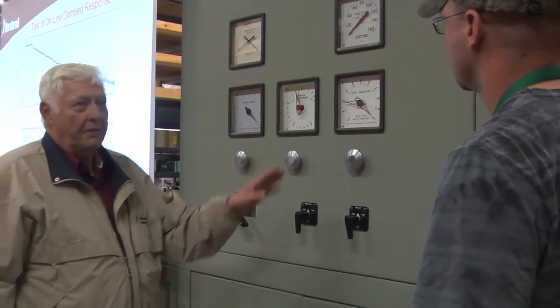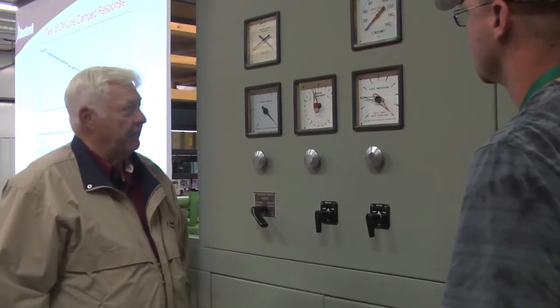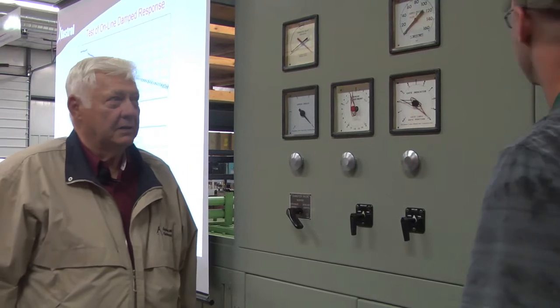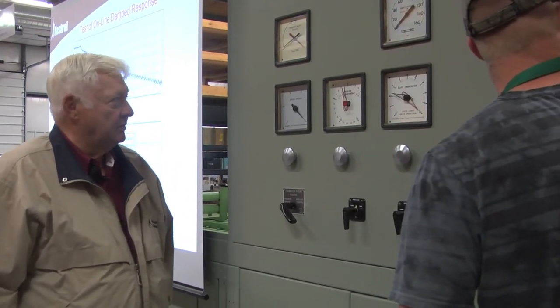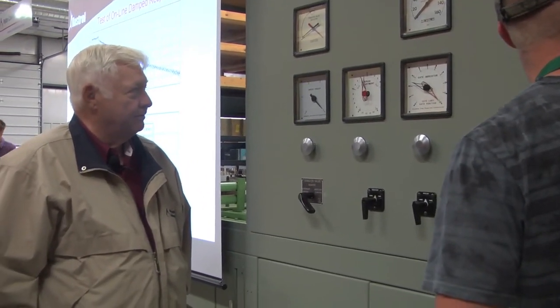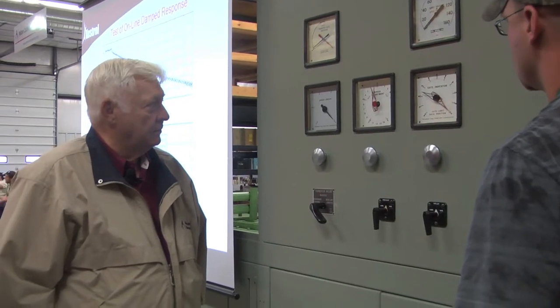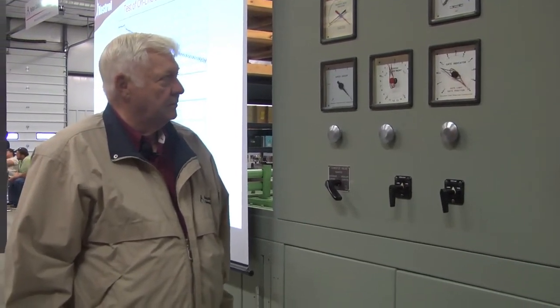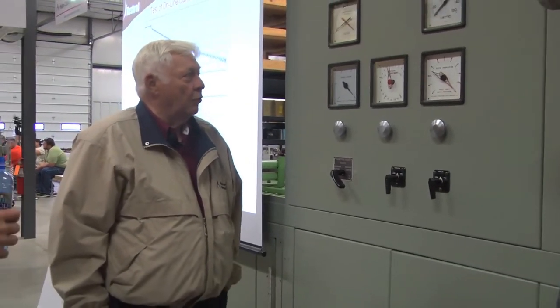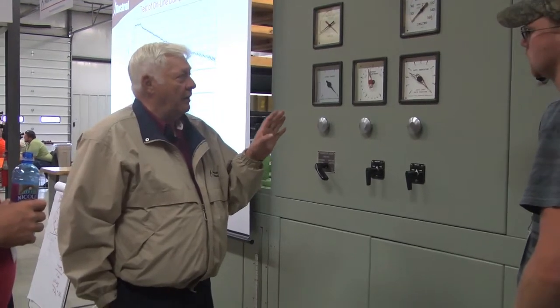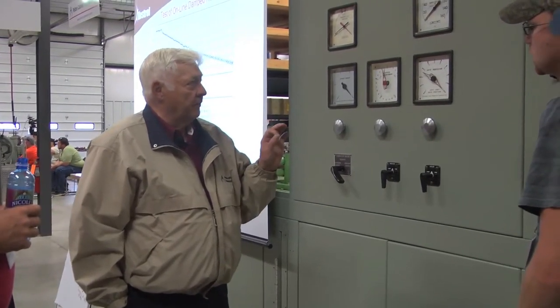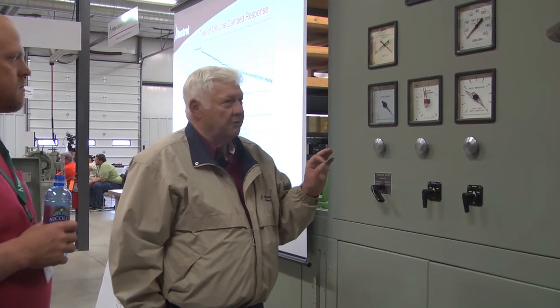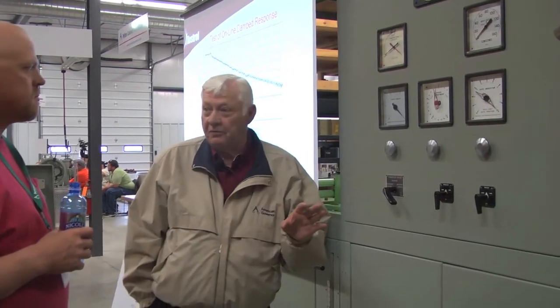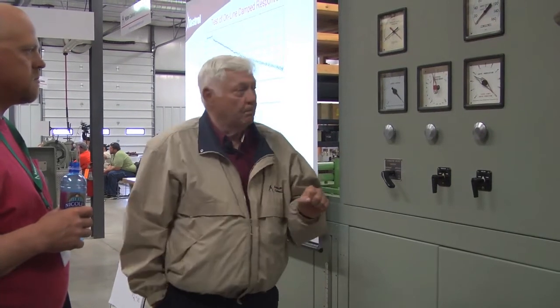Now that's more what I would expect to see in the field, something that fast. That was over a half a turn down farther than it should. That's what it acted like to me, that it was way open too far. Now with this, I would be pretty well convinced that if I got separated from the system, although I'm loading faster now than I was before, I would still be stable for a frequency upset.